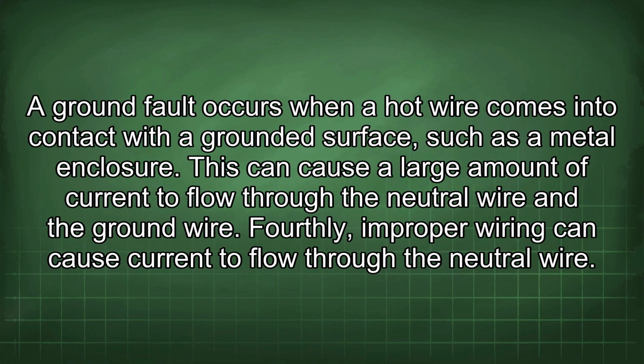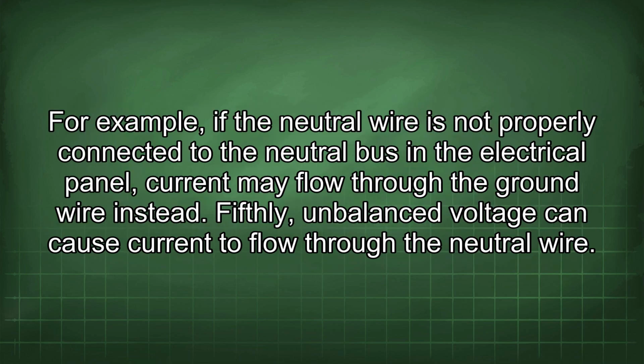A ground fault occurs when a hot wire comes into contact with a grounded surface, such as a metal enclosure. This can cause a large amount of current to flow through the neutral wire and the ground wire. Fourthly, improper wiring can cause current to flow through the neutral wire. For example, if the neutral wire is not properly connected to the neutral bus in the electrical panel, current may flow through the ground wire instead.